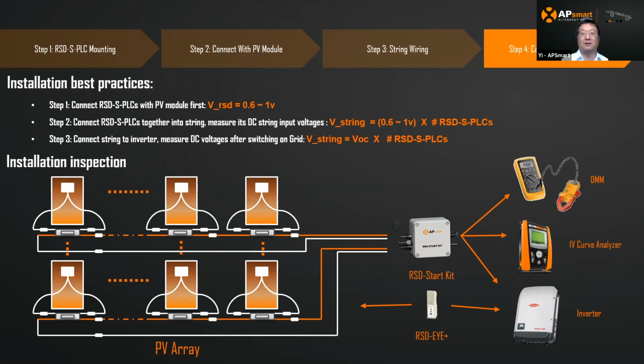When you turn on that tool, it has a transmitter inside to generate the signal, and that immediately activates the modules in the string. You can measure on the output exactly what the voltage is from the DC side, or use the IV curve analyzer to do the IV curve, or even directly hook up with your Fronius inverter, doing the self-check before you turn on the switch. Then you can actually do some IV curve independently with your inverter.